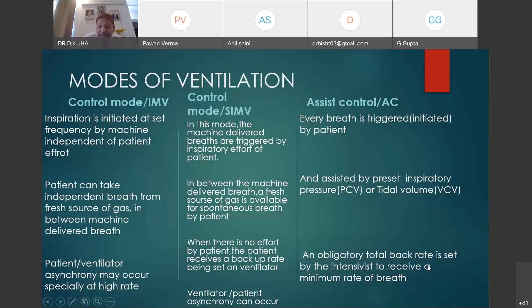Now the assist control, this is a very important mode, AC. Nowadays there is requirement of AC, temperature is hot and humid, so this is very important. AC, remember, AC means assist control. In this mode every breath is triggered by the patient, meaning initiated by the patient and assisted by preset inspiratory pressure or tidal volume as per the mode of ventilation. So patient triggers the breath, the inspiratory phase is controlled by the machine, and an obligatory total backup rate is set by the intensivist to receive a minimum rate of breath. It will be clear in next slide, my dear resident.